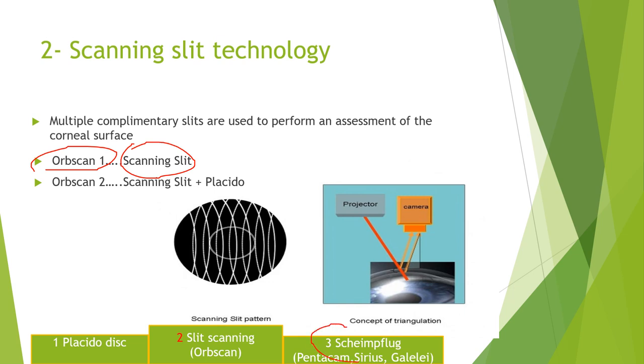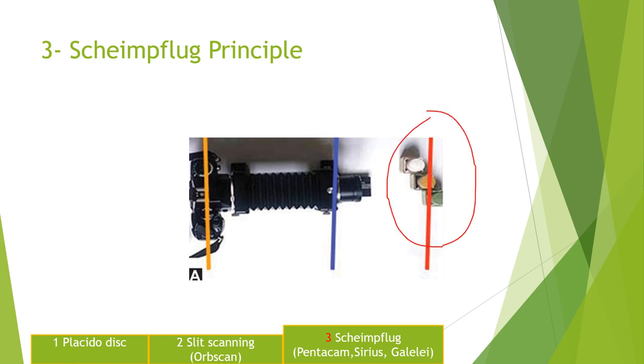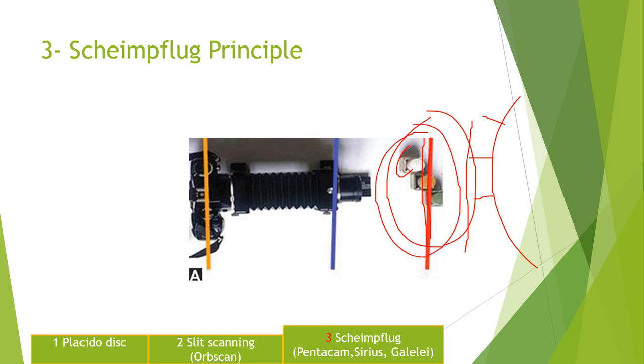Now let's move to the third one which is the Scheimpflug technology. Look — this is a camera and it is taking a photograph of an object that has three colors. The middle color is right in line with the camera so the focus will be better on the middle color, while the other colors will be slightly out of focus. We don't want that with the cornea because the cornea is curved, so we want every part of the cornea to be focused. A simple camera will not solve the problem — we need to use the Scheimpflug principle.